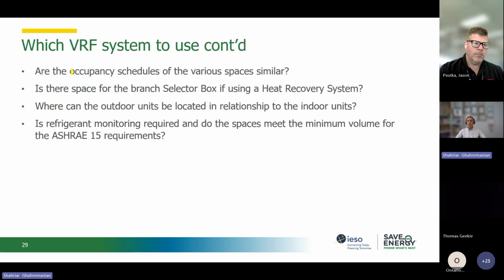The other question is how is the occupancy schedule in different spaces, and is there a space branch selector box we need or not? Because that's going to add extra cost to our design, basically. And then where we can put the outdoor unit. This is also an important factor, both because of the efficiency of the outdoor unit and also the length of the refrigerant piping that we need. And then there are standards, ASHRAE 15 and ASHRAE 34. These are the standards from ASHRAE. I will show you later on. There are other standards that we can use if we are going to consider a VRF, or variable refrigerant flow, for our buildings.